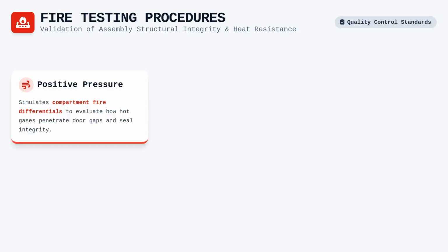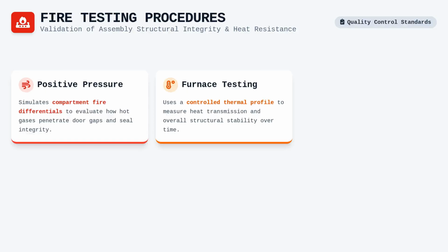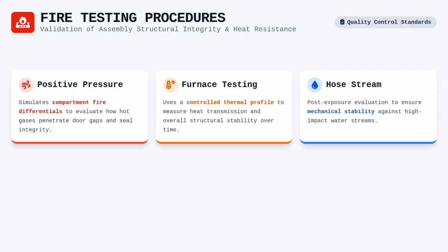Testing procedures for these assemblies involve rigorous exposure to standard fire tests, which often include both positive pressure and hose stream evaluations. Positive pressure testing is particularly significant because it simulates the actual pressure differentials generated by a compartment fire that forces hot gases through door gaps. During the furnace test, the assembly is subjected to a controlled thermal profile that measures heat transmission and structural integrity over time. Following the fire exposure, the hose stream test is conducted to ensure the assembly maintains its physical stability against the mechanical impact of firefighting water streams.